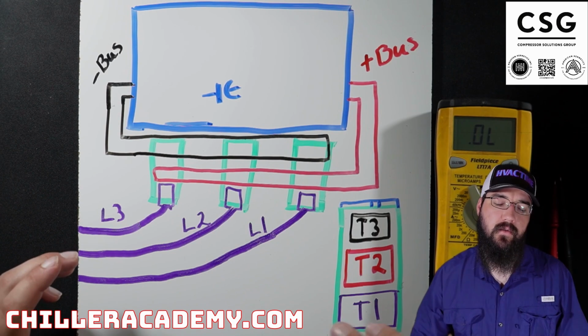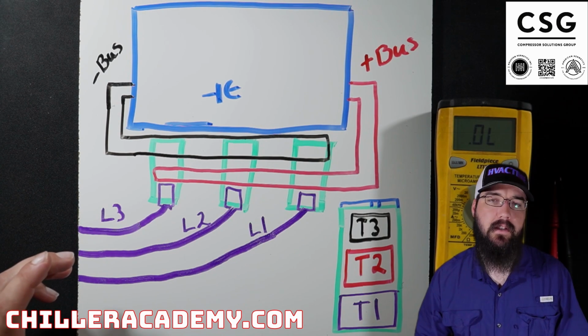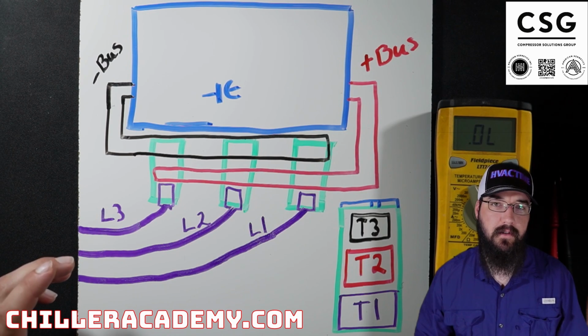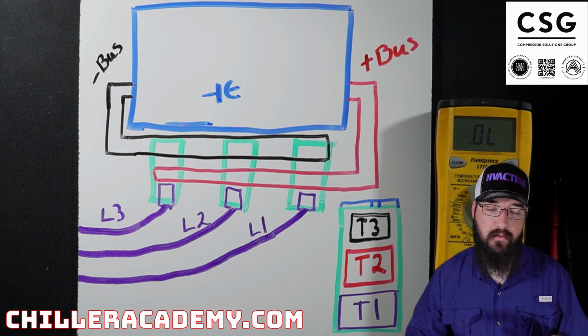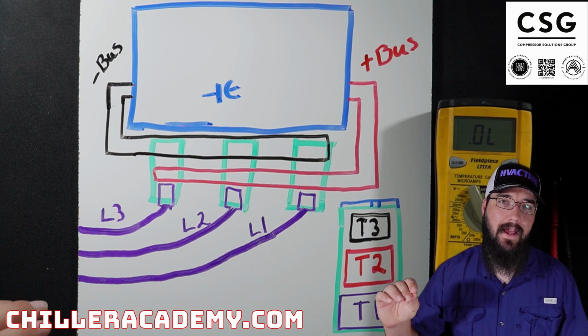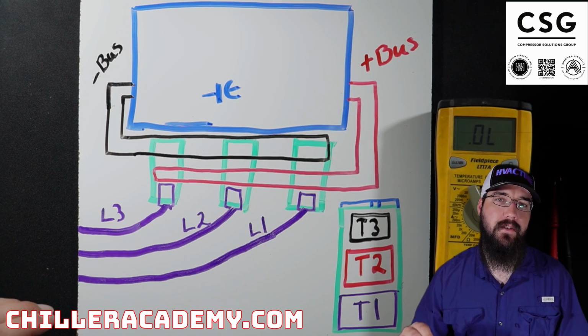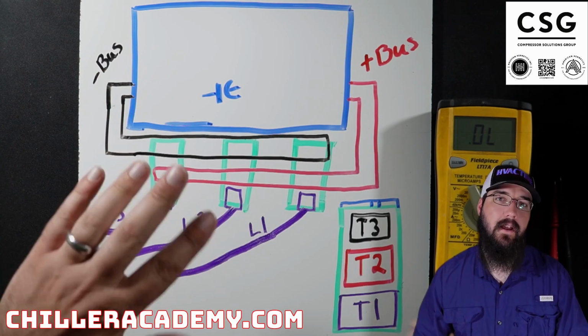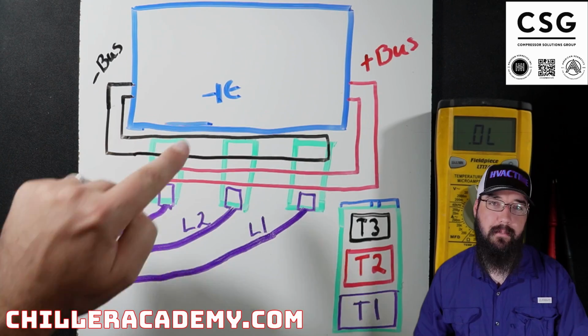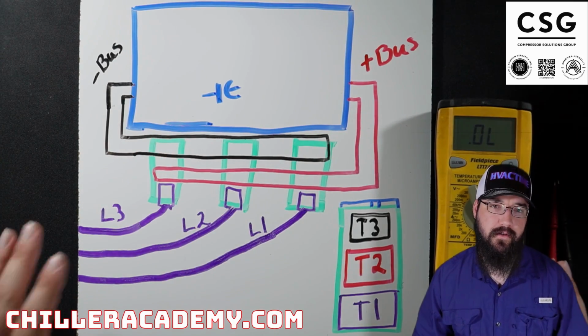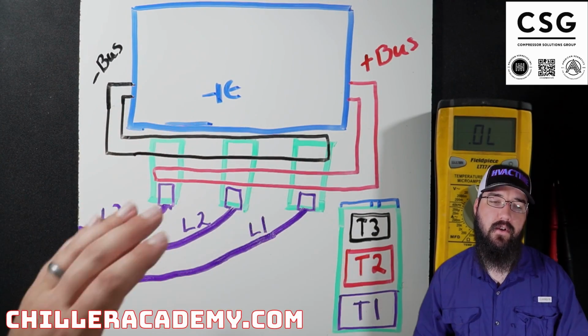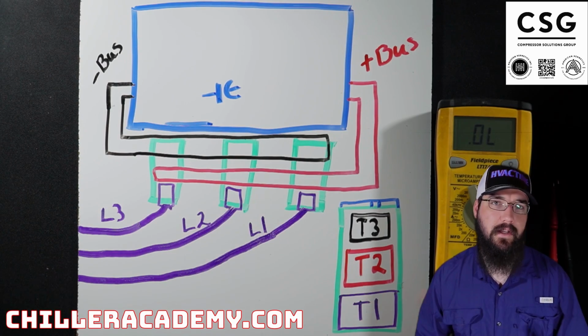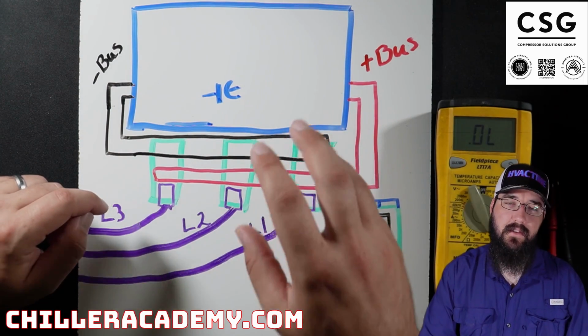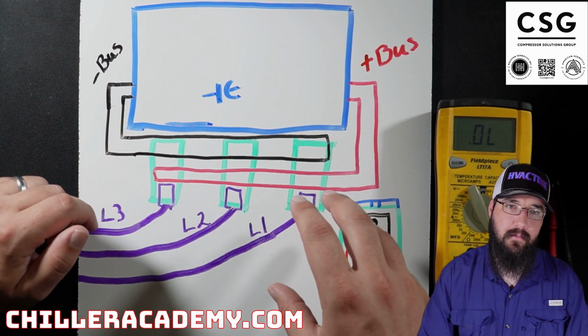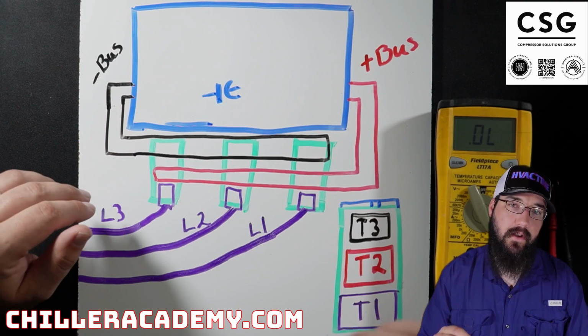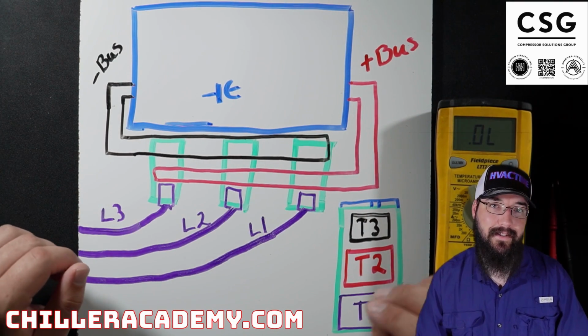It is really critical that power be completely turned off to the VSD assembly, to the whole chiller. Nothing should be powered up. And we need to make sure that the DC bus back here has fully discharged. This is full of capacitors, and they're going to store some energy. That has to be discharged before we start any kind of testing. If this is not done, this can create a backfeed through your meter. Stuff can get broke and you could get hurt. So please take that seriously.